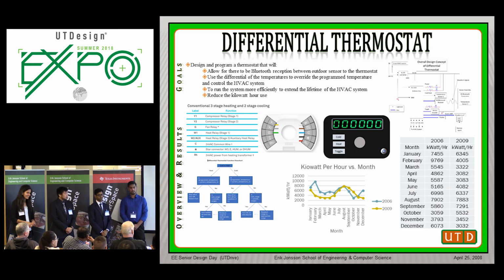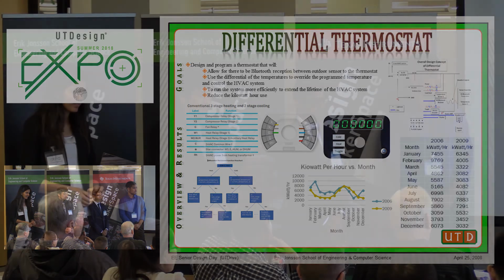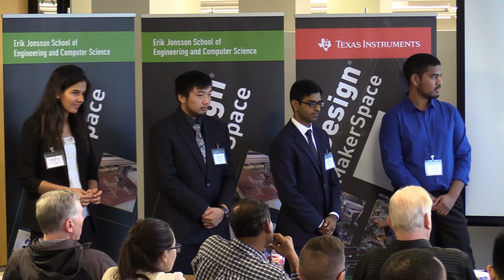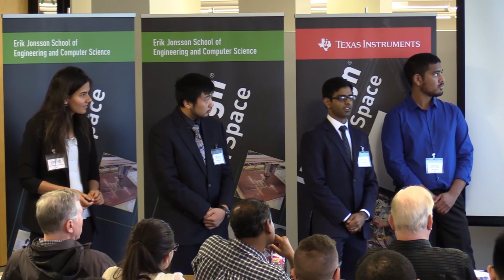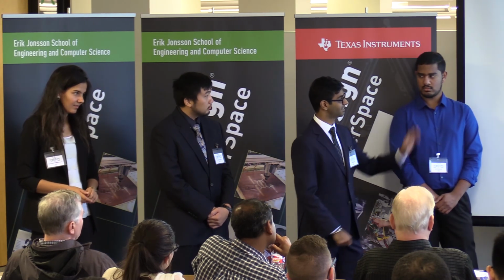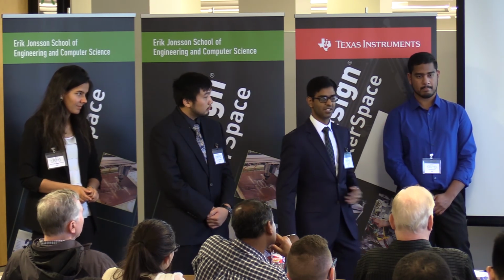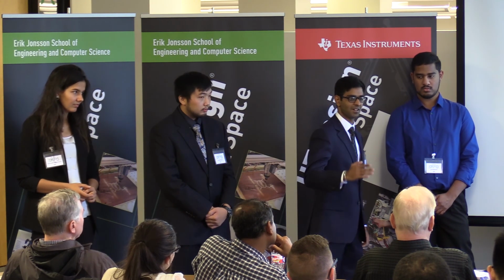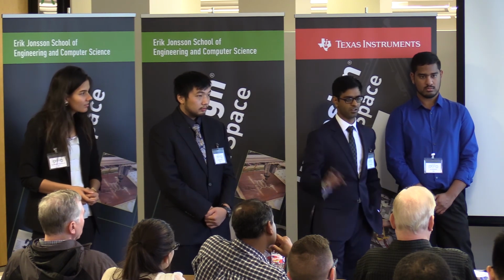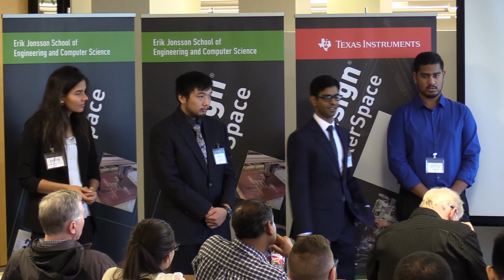So how much current are you allowed to take off that 24 VAC that you're gonna use for your power? From what I remember, it was like 1 amp. Is there a spec that says that you can pull an amp? Yeah, there is. I'm pretty sure it said 1 amp, but I did look up everything, and there's a certain point at which it'll cap out. But we're not gonna approach that point at all. Like ours is way under that. Okay.